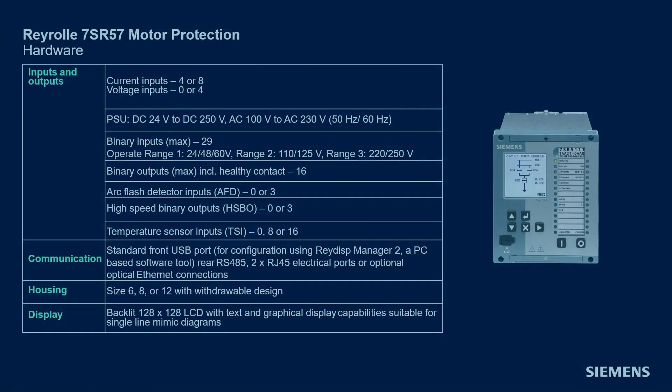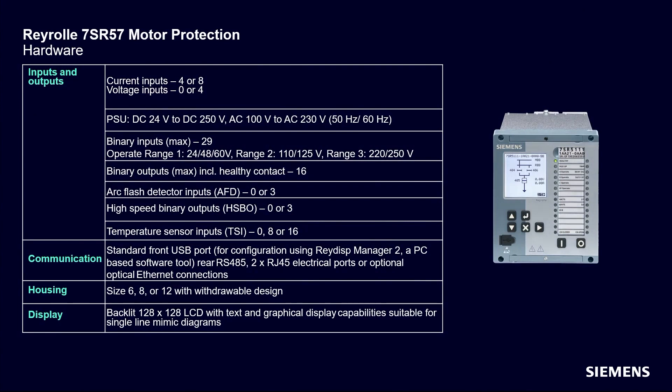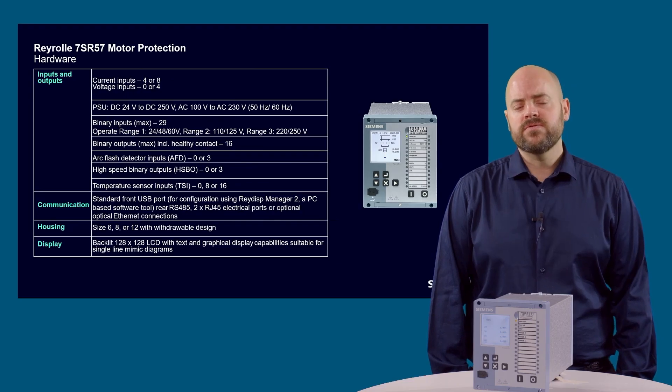The device has a rear RS485 port and dual ethernet ports with either electrical or optical interfaces. Communication protocols include IEC 61850, Modbus TCP, DNP3 TCP and also redundancy protocols. The smaller S6 devices have a case width of 153mm, the next size S8 is 205mm and the largest S12 is 308mm wide. A large graphical display makes it easier to view device information.